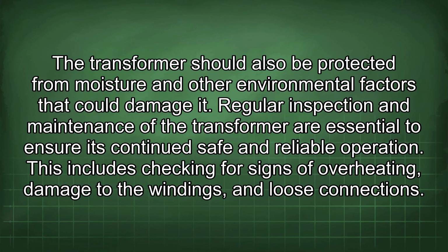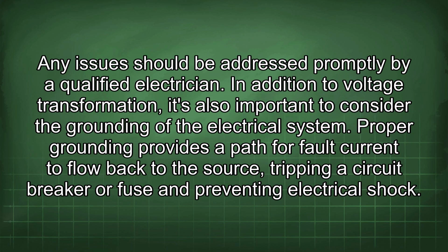The transformer should also be protected from moisture and other environmental factors that could damage it. Regular inspection and maintenance of the transformer are essential to ensure its continued safe and reliable operation. This includes checking for signs of overheating, damage to the windings, and loose connections. Any issues should be addressed promptly by a qualified electrician.